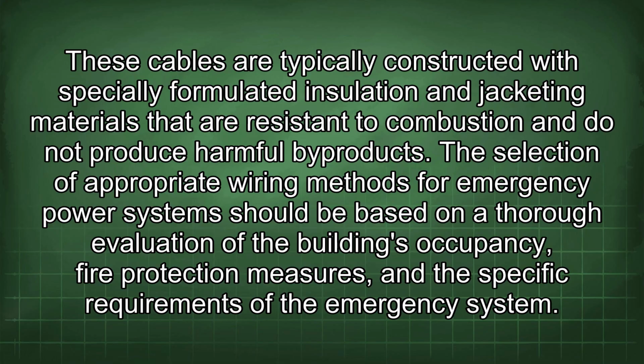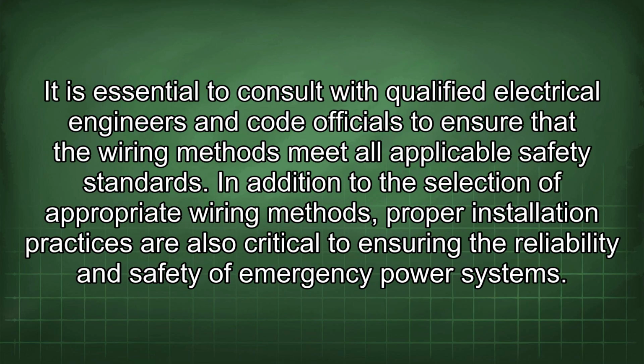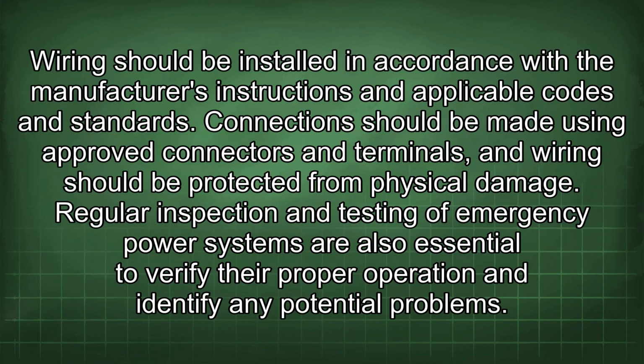The selection of appropriate wiring methods for emergency power systems should be based on a thorough evaluation of the building's occupancy, fire protection measures, and the specific requirements of the emergency system. It is essential to consult with qualified electrical engineers and code officials to ensure that the wiring methods meet all applicable safety standards. In addition to the selection of appropriate wiring methods, proper installation practices are also critical to ensuring the reliability and safety of emergency power systems. Wiring should be installed in accordance with the manufacturer's instructions and applicable codes and standards. Connections should be made using approved connectors and terminals, and wiring should be protected from physical damage.